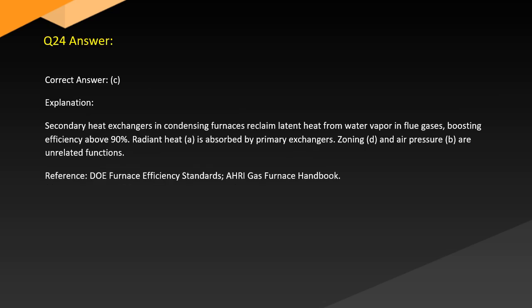Answer. Correct answer, C. Explanation. Secondary heat exchangers in condensing furnaces reclaim latent heat from water vapor in flue gases, boosting efficiency above 90%. Radiant heat, A, is absorbed by primary exchangers. Zoning, D, and air pressure, B, are unrelated functions. Reference: DOE Furnace Efficiency Standards, the ARI Gas Furnace Handbook.